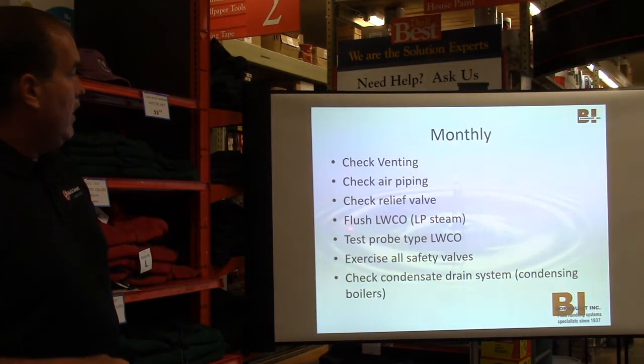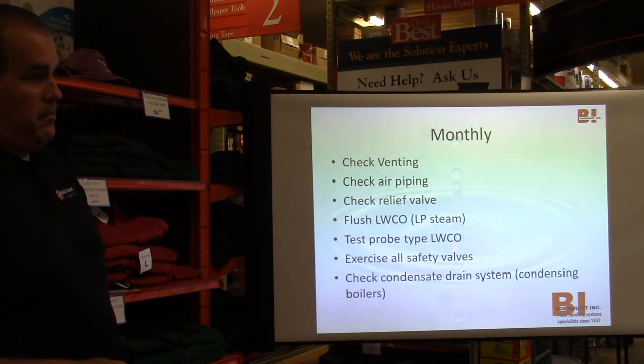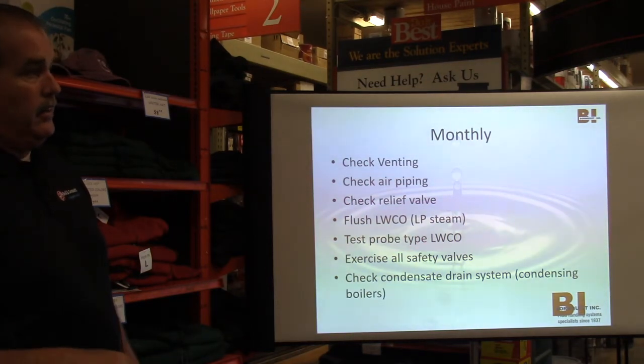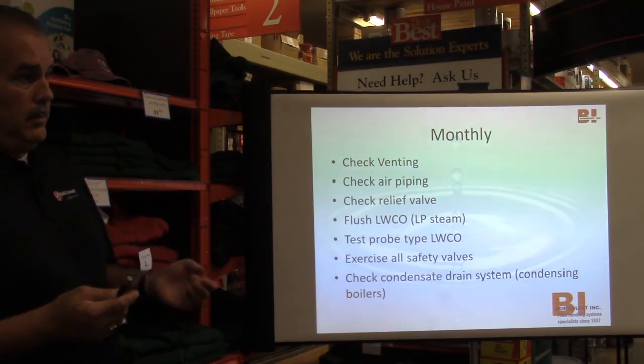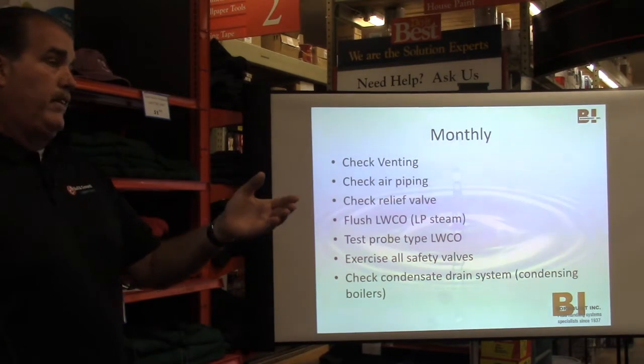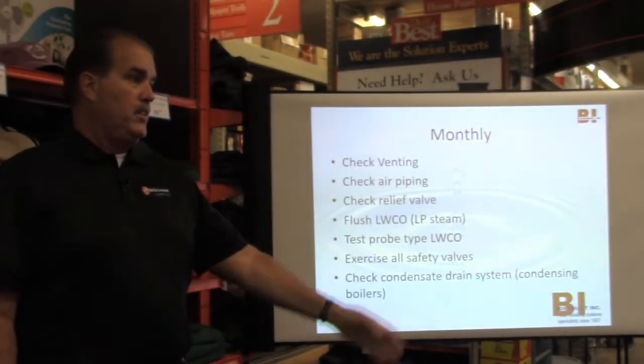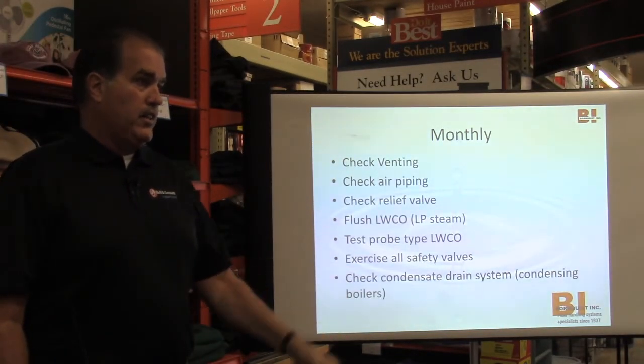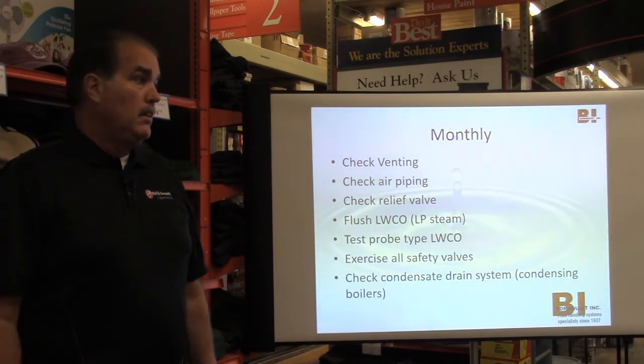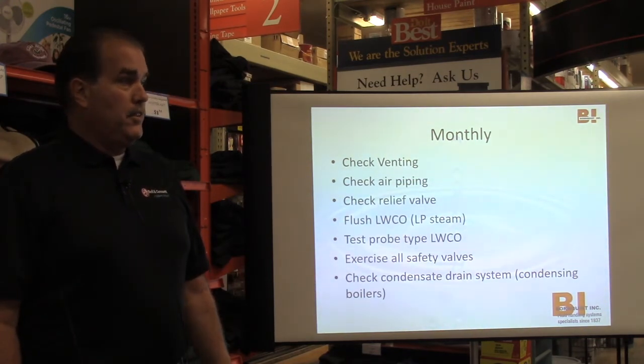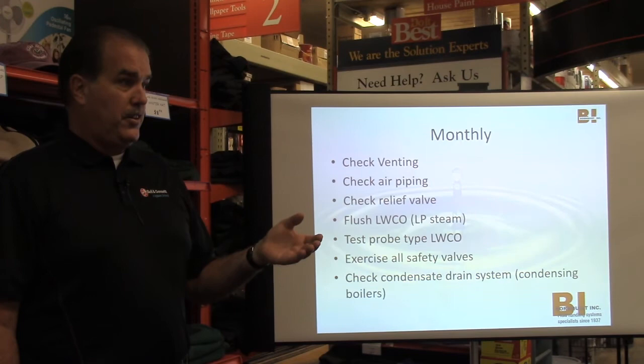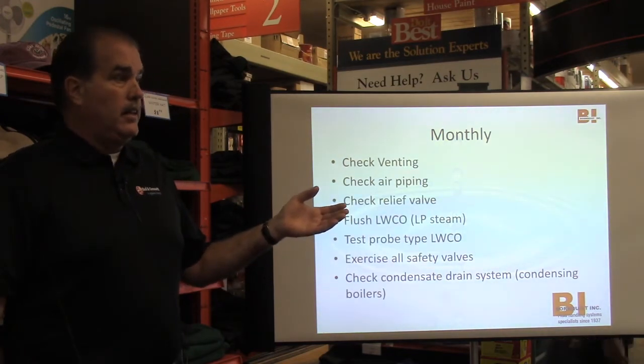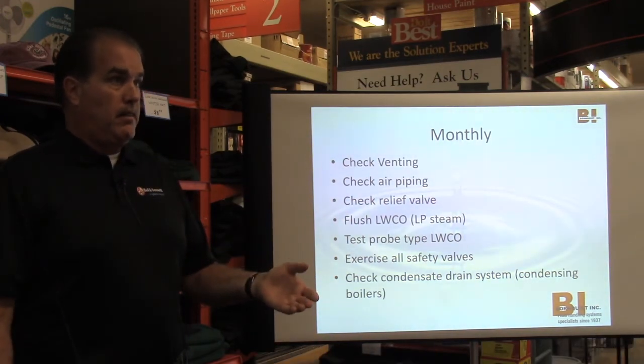Here's where we say flushing monthly on a low water cutoff is fine if your system's fairly clean. If you have a dirty system, here's the way to figure it out. You flush it in a week. A week later, you flush it, and nothing comes out. Wait two weeks. Flush it in two weeks. If nothing really comes out that's dirty, you can extend it. If you flush something out and dirt's coming out, guess what?